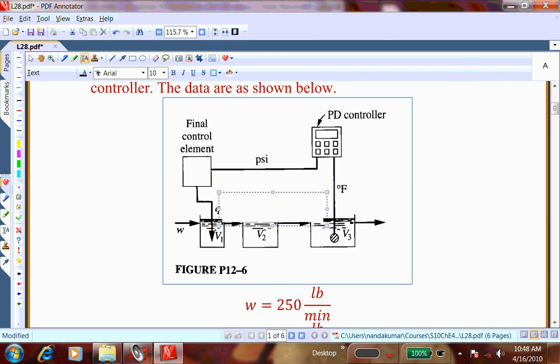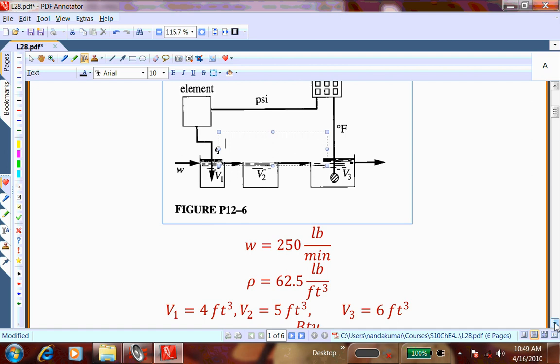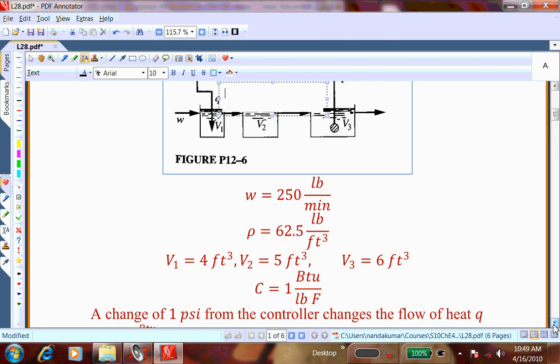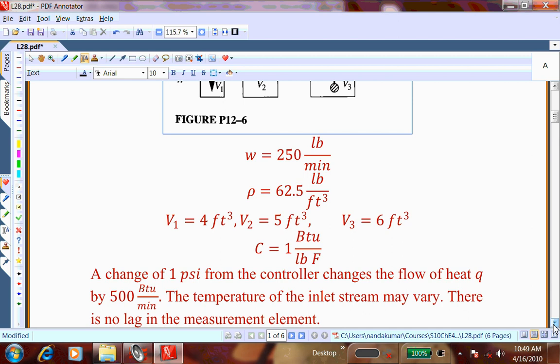We can play with many things to learn about the dynamic response and see how to get this system under control by tuning the control parameters. The problem description gives: flow rate W = 250 pounds per minute, water with density ρ = 62.5, and three different tank volumes. A change of one PSI from the controller changes the heat flow by 500 BTU per minute — that gives the gain relationship between the controller and the final control element.